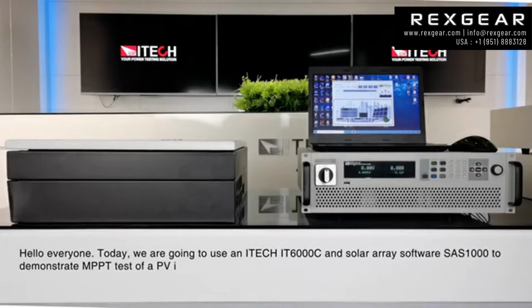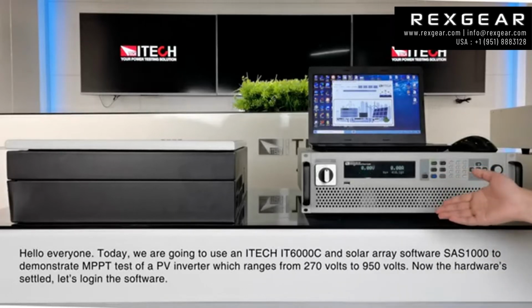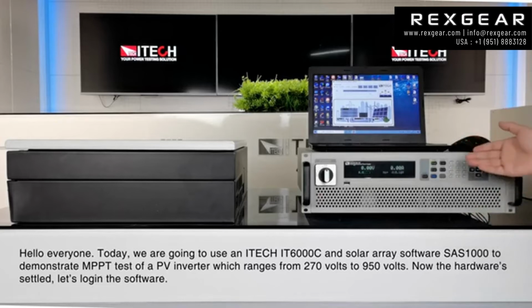Hello everyone. Today, we are going to use an ITECH IT6000C and solar array software SAS1000 to demonstrate an MPPT test of a PV inverter, which ranges from 270 volts to 950 volts. Now the hardware has settled. Let us log in the software.